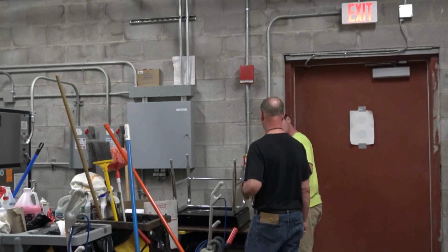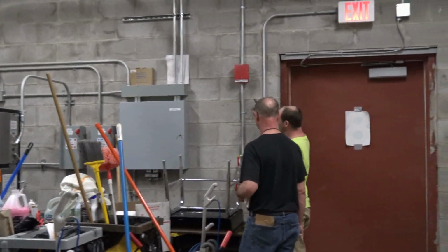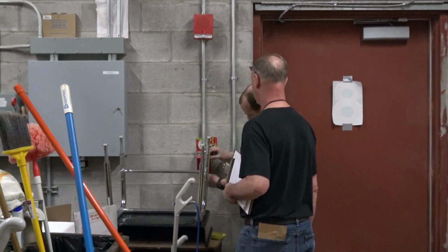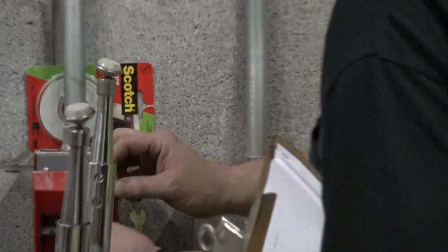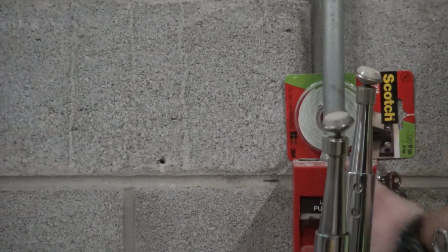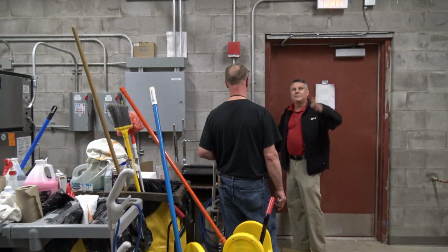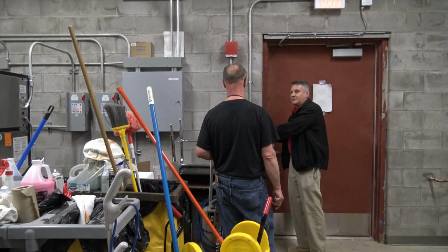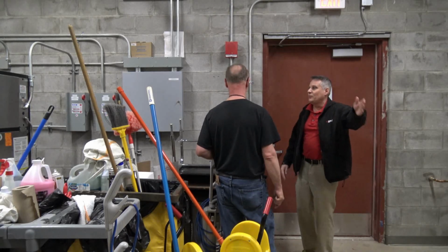Toggle right there. When you pull that thing, it goes up. Now, to reset it, you open that up, you push it back down, and pull that back in. Now, I would reset immediately. What you want to do is activate it, make sure it activates, then reset it, because if you don't reset this, it stays stuck on the panel until you reset.